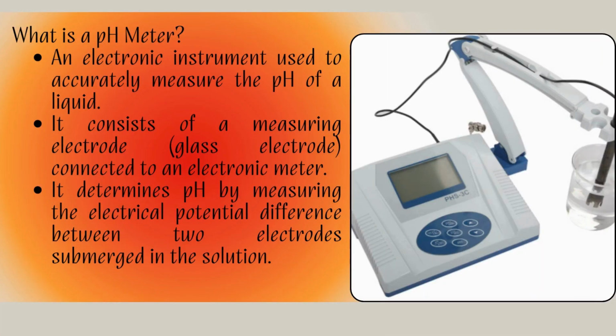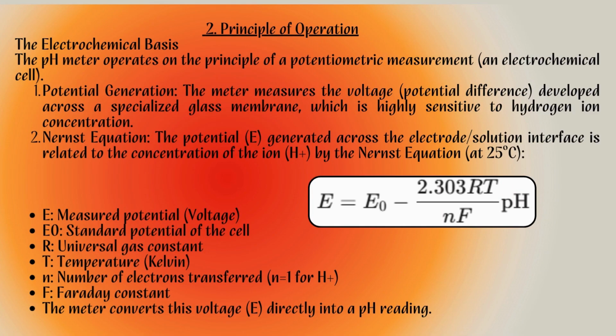Now to measure this value accurately, we use an electronic instrument called the pH meter. As you can see in the image, it's an electronic instrument that consists of a probe, usually a combination electrode, connected to a meter. It does not use chemical indicators like litmus paper. Instead, it measures the electrical potential difference between two electrodes submerged in the solution, which brings us to its operating principle. The pH meter operates on the principle of potentiometric measurement.